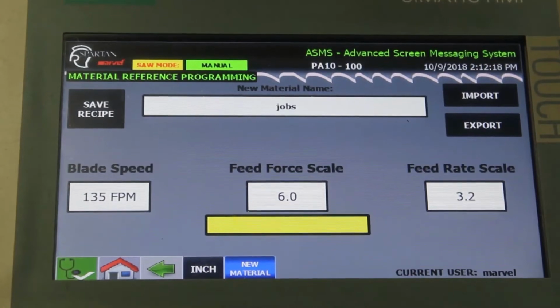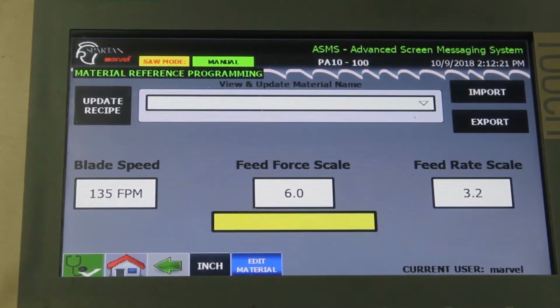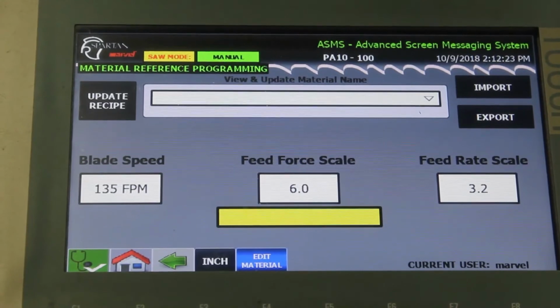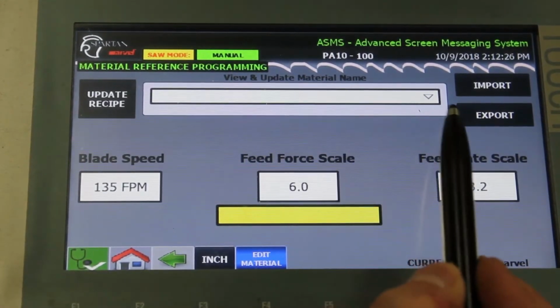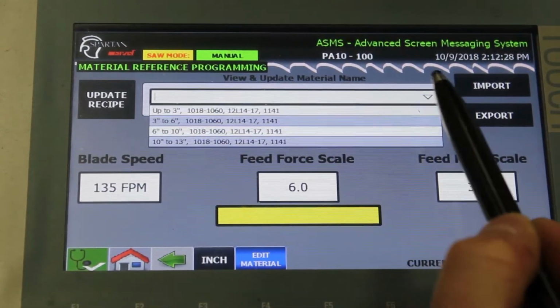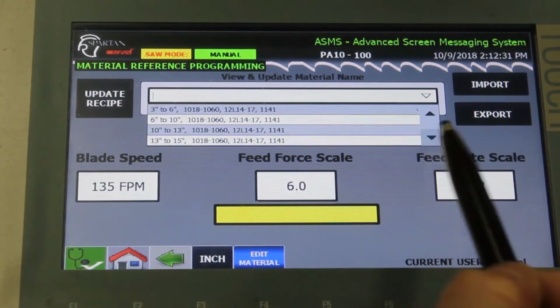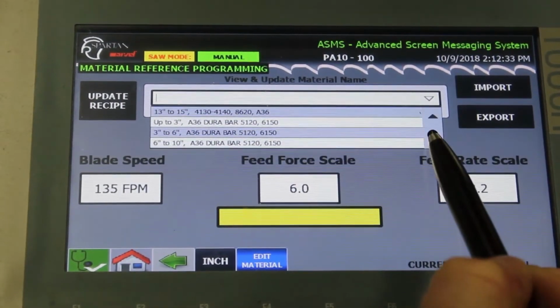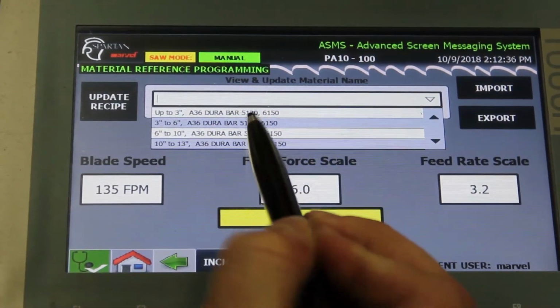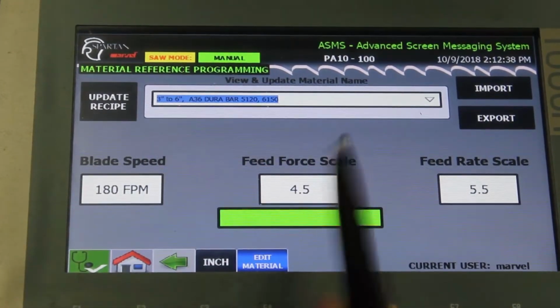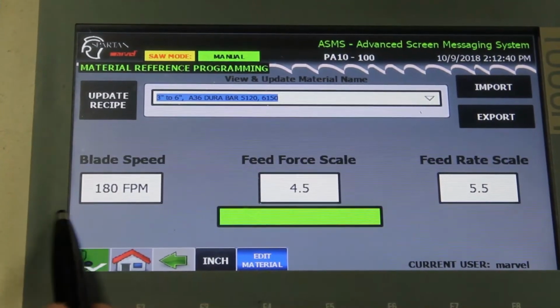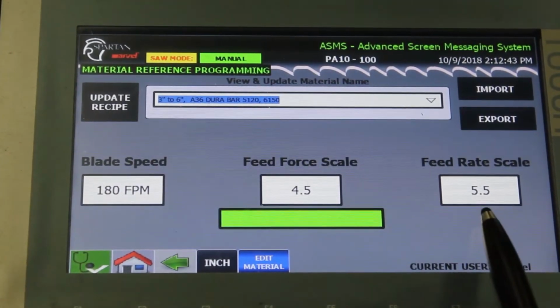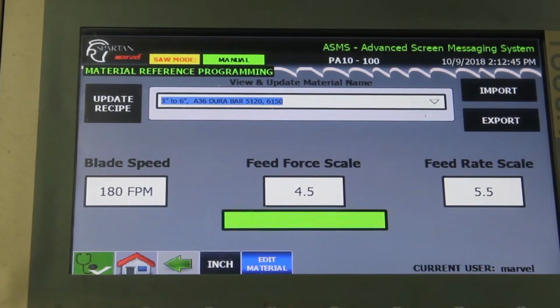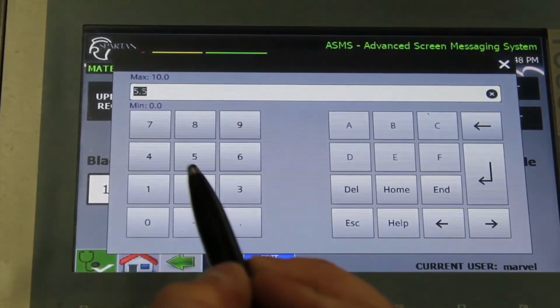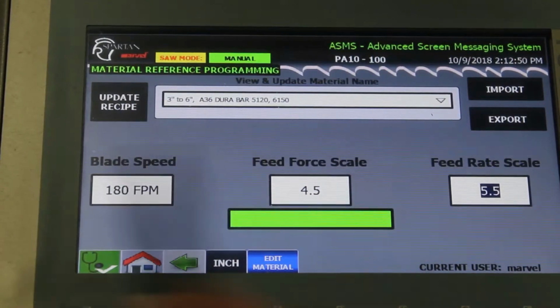To edit an existing material, press the Material button till it changes into edit mode. You'll see that our naming box has now turned into a drop-down menu. This drop-down menu displays all of the current materials in the system. To edit one, simply press it, which will display it here. It also displays the blade speed, feed force, and feed rate scale for this material. To edit it, simply press on a box, enter a new value, and click Update Recipe.